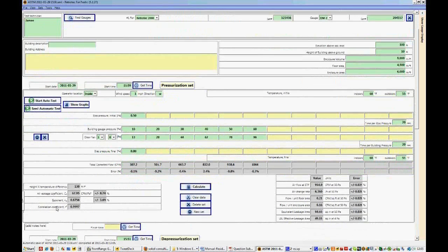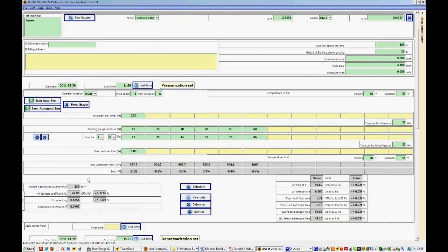So these are some of the results that you would see in the deviation statement. For instance, the height times temperature difference. This must be below 1180. And it's based on the temperature difference between indoors and outdoors and the height of the building above ground.